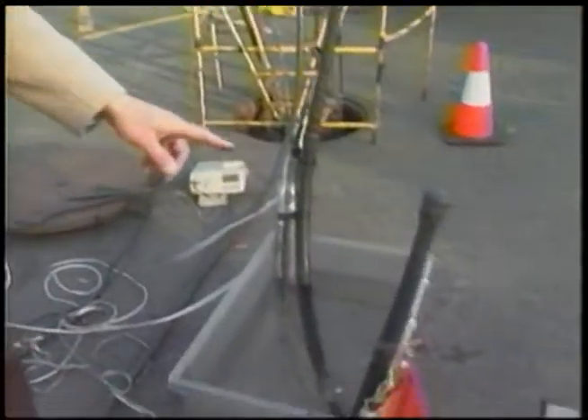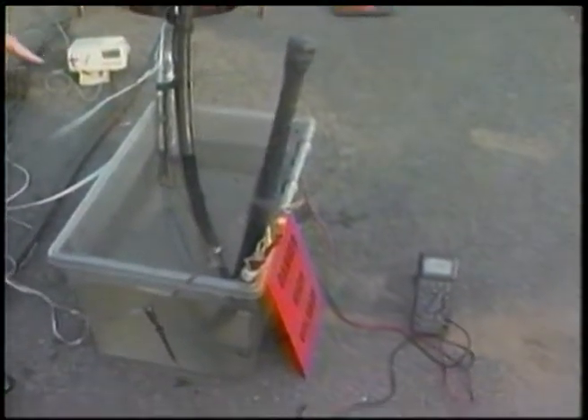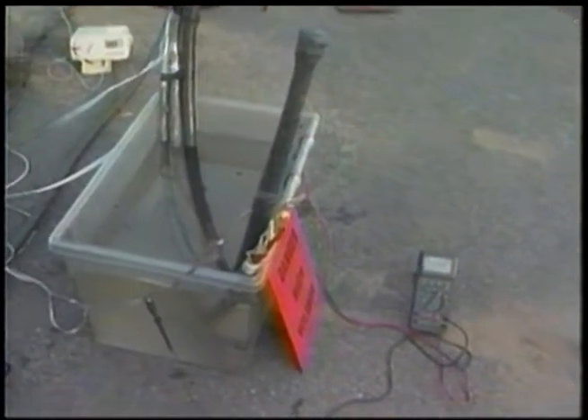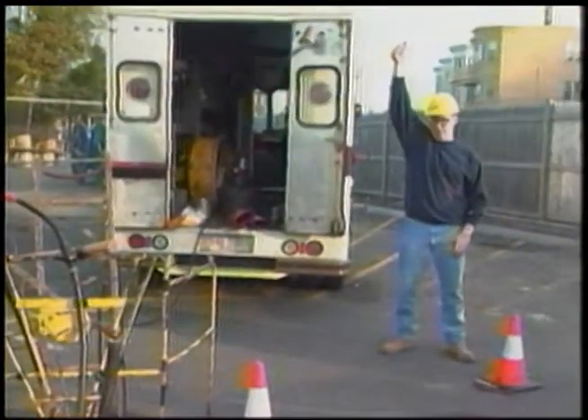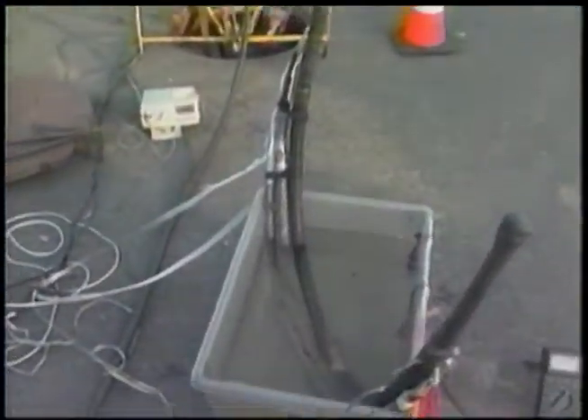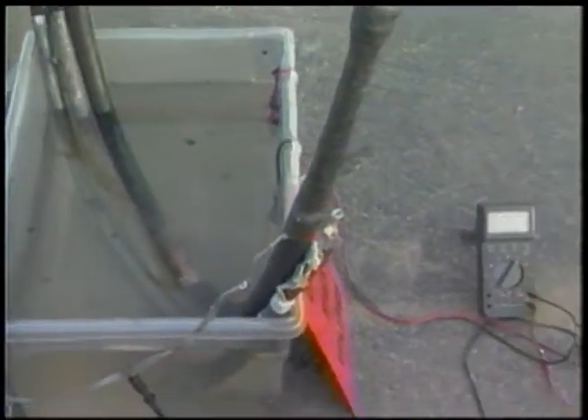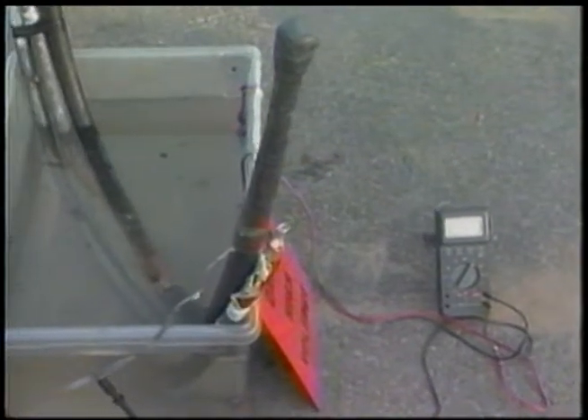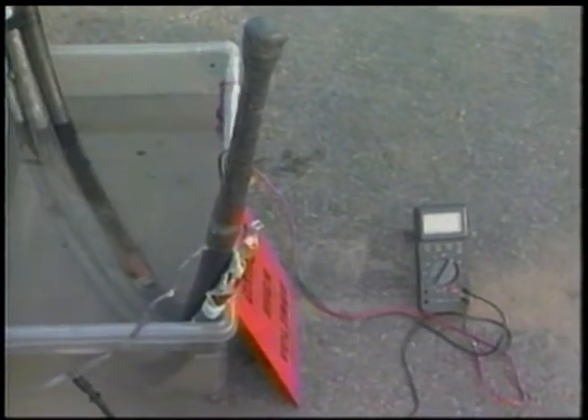Now that we've filled the bucket with water, we've attached a meter to the two probes. This is a regular meter. There is no multiplier on it. It's reading directly. Okay, Dennis, energize the fault. With the fault in the water, the meter is measuring the black probe, which is 6 inches away, and it's measuring about 5 to 6 volts.